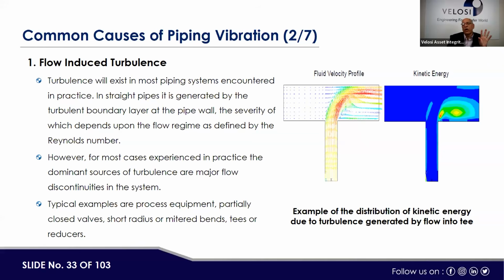Similarly, when we talk about pressure reduction valves, they are more critical, and if pressure reduction is required more than a certain limit, then we call it a multi-stage pressure drop system, right? Rather than dropping the pressure through one valve, you may have to install two valves to drop the pressure in two stages. So this is a normal configuration in valving, but this relates to control valves. As long as it is a normal gate valve, globe valve, or ball valve used for isolation of the flow, those are full bore valves, so they do not create any problem in vibration as such.